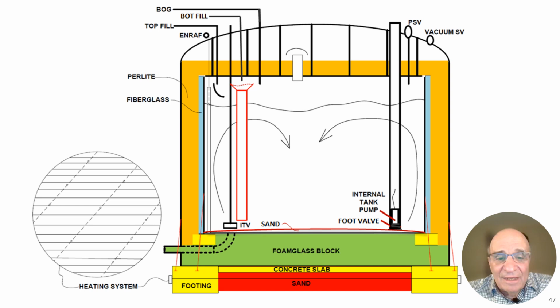Now, the blue layer that's shown here is fiberglass. And why would they want fiberglass insulation in here alongside the perlite? It's typically about a foot thick of fiberglass. And the reason is because the tank, when you cool it down, shrinks in size. A large tank will shrink about 6 inches in diameter. And as it does that, this perlite drops down and compacts.